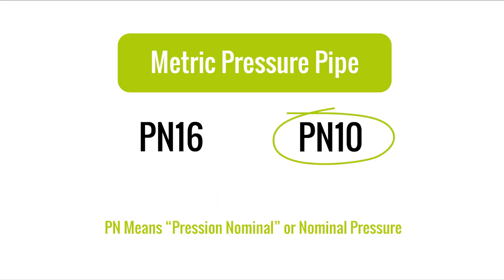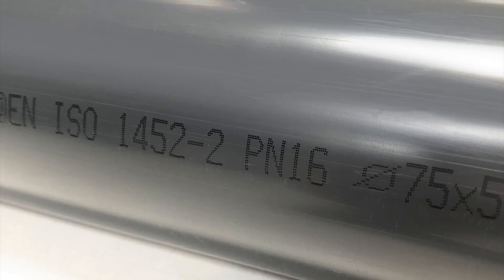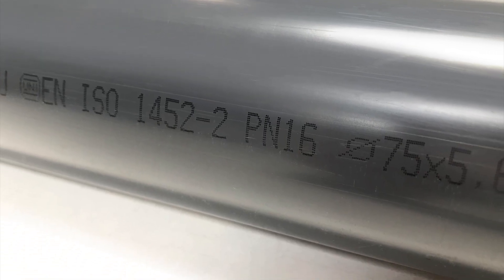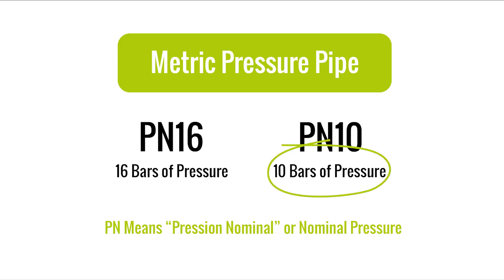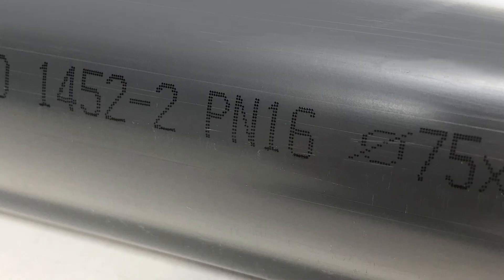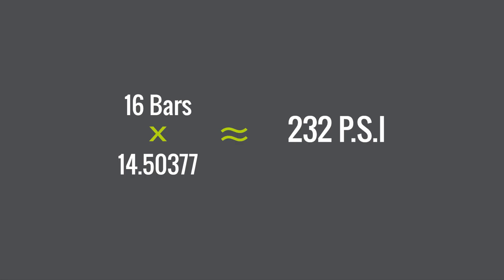Metric pressure pipe will be assigned a PN number, such as PN16. This PN number is a direct indication of the pressure rating in bars. So a PN16 pipe is rated for 16 bars of operating pressure, which converts to approximately 232 psi.